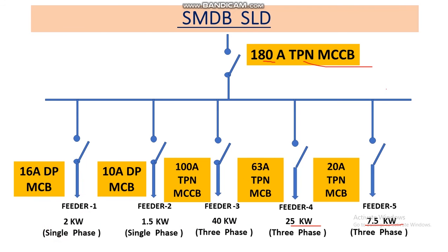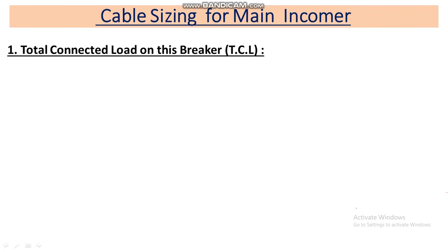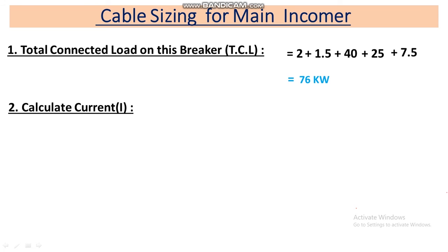Now let's calculate the cable size for individual feeders. First, let's calculate the cable size for the main incomer. We have to sum all the feeder loads: 2 + 1.5 + 40 + 25 + 7.5 kilowatts, which equals 76 kilowatts. So our total connected load on the main incomer is 76 kilowatts. Since this is a three-phase load, we use the three-phase power formula to calculate the current.